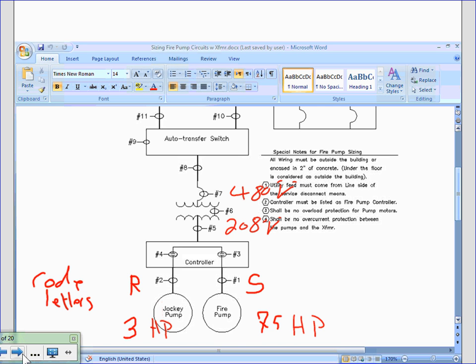And what do you have now? Why would you want to run them at 208, besides that the jockey pump and the fire pump are rated at 208? Is there any other logical reason? Maybe. If you have a 480, yeah, you'd be fooled to use this system. Judgment. If you have a 480 coming to your building, it would be foolish to put in a transformer and lower them down to 208, 120.